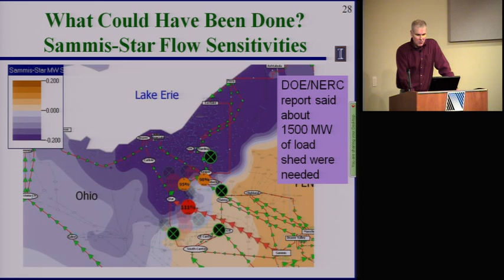We thought everything was working fine, except alarms weren't working. Turns out that their displays weren't refreshing very fast either. And if you're in a control center in a stressful situation and you try to load a display and it takes like 10, 15, 20 seconds, it doesn't sound like a lot, but if you start waiting for that display to come up while the phones are ringing, people are saying, what's going on? That's a significant issue. We didn't know this in the interviews, and nobody actually shared it with us, but we didn't know to ask. We just thought the alarms had hung up.